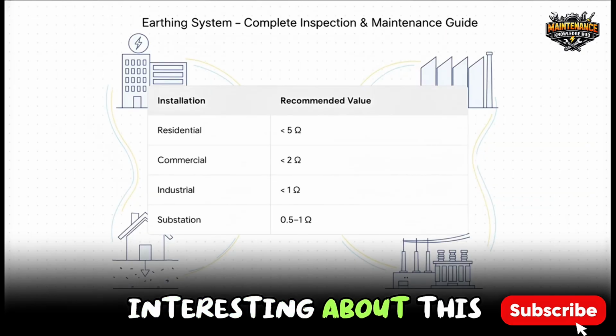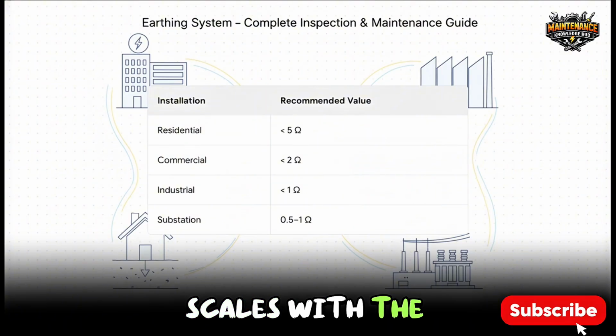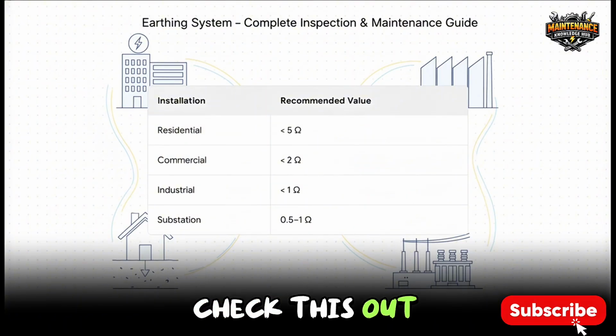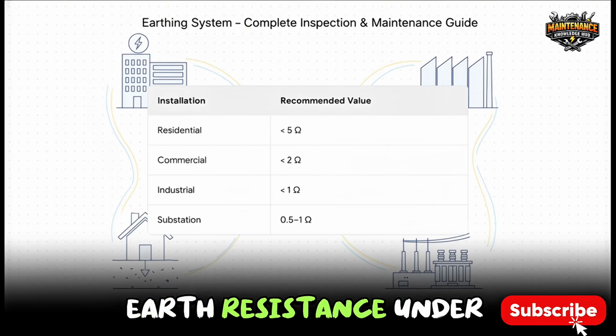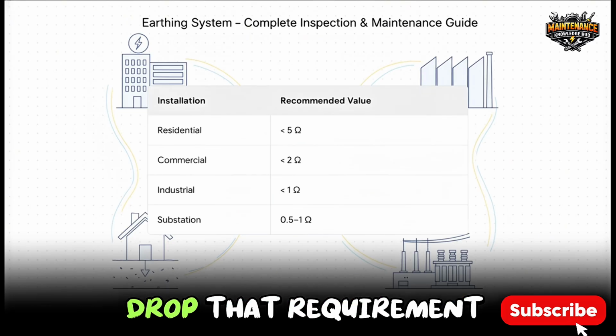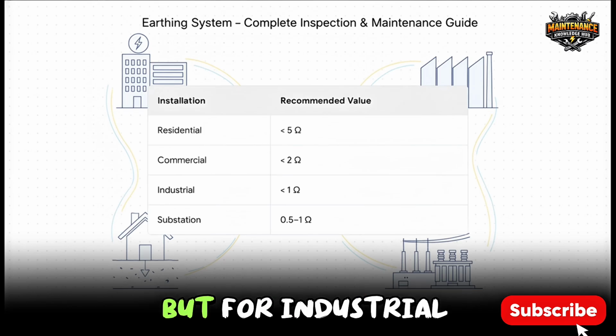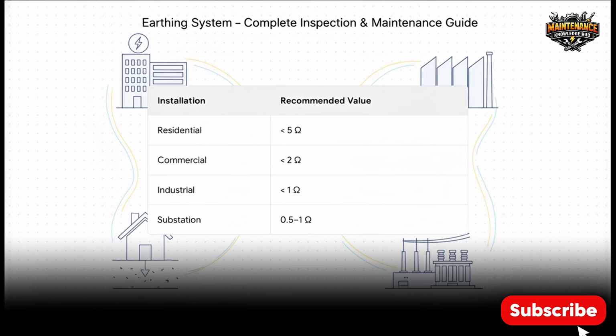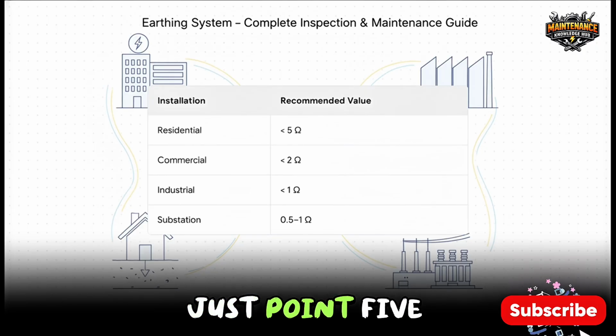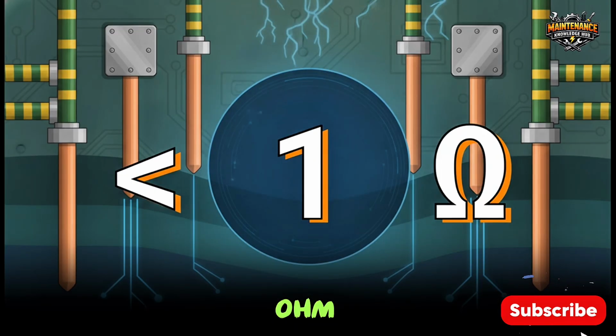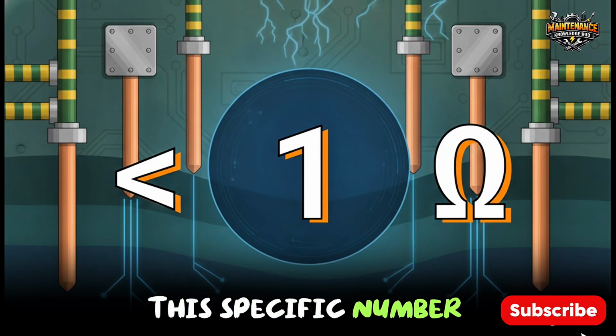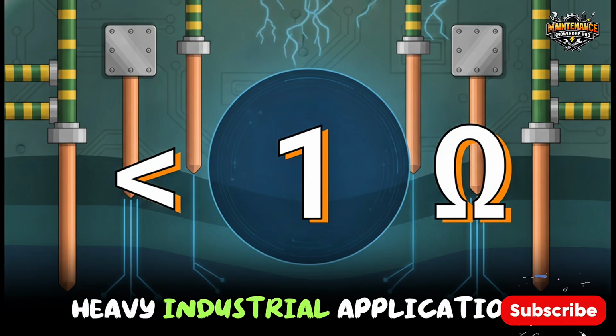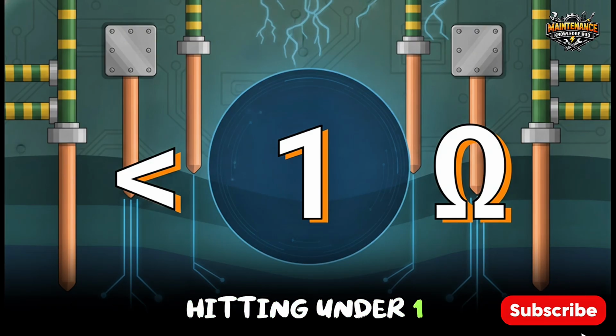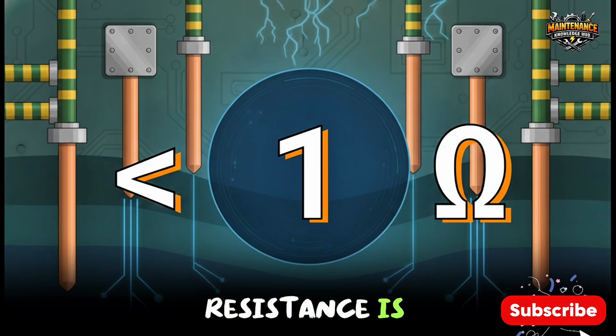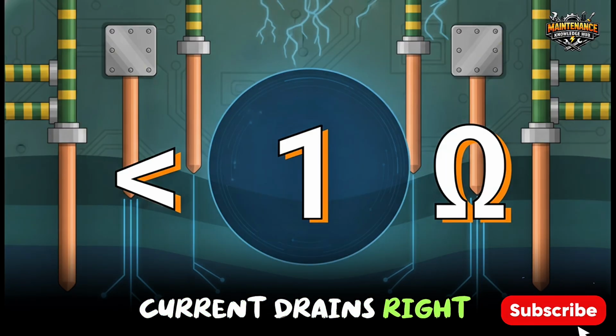You're basically trading a tiny bit of absolute precision for massive gains in your maintenance speed. Now, what's really interesting about this is how the required resistance basically scales with the complexity of the installation. Check this out. For a standard residential setup, you want your earth resistance under 5 ohms. Commercial buildings drop that requirement down to under 2 ohms. But for industrial sites and sensitive electronics, you need under 1 ohm. And substations require an ultra-conductive path of just 0.5 to 1 ohm. Less than 1 ohm. I really want to emphasize this specific number right here. For sensitive electronics, heavy industrial applications, critical infrastructure, hitting under 1 ohm is the ultimate goal. The lower that resistance is, the faster and safer that deadly fault current drains right into the earth.